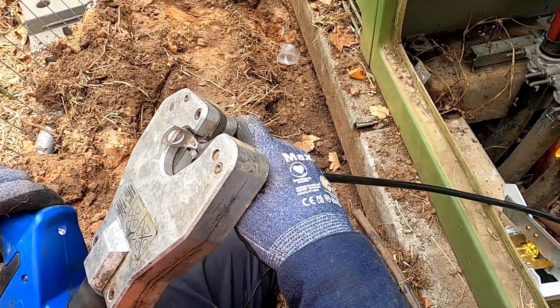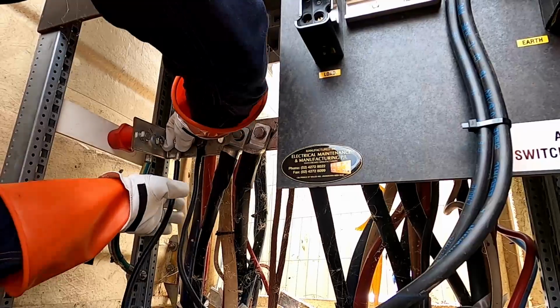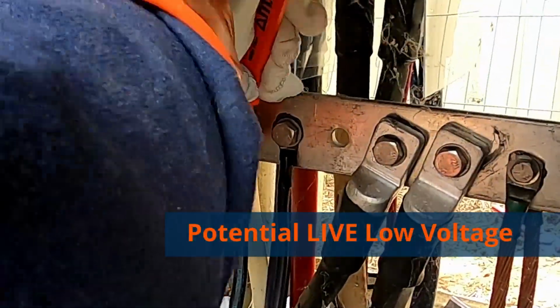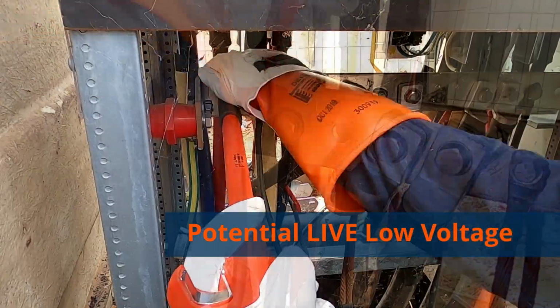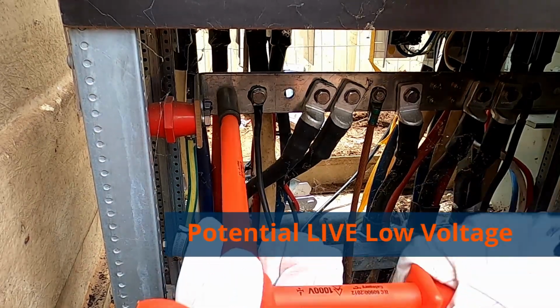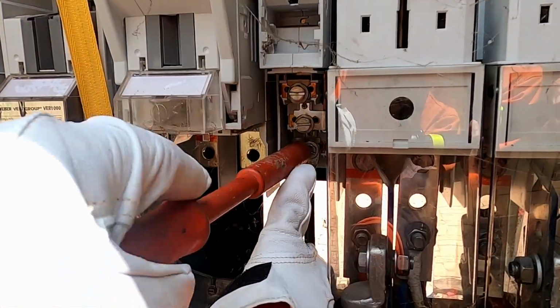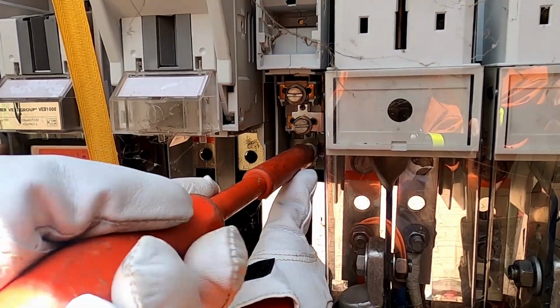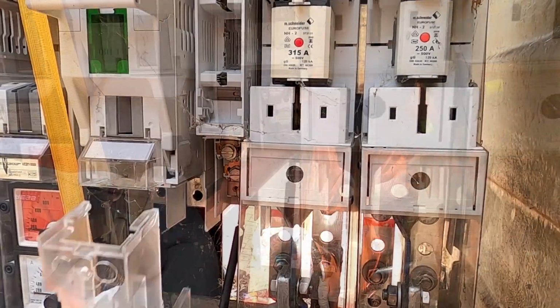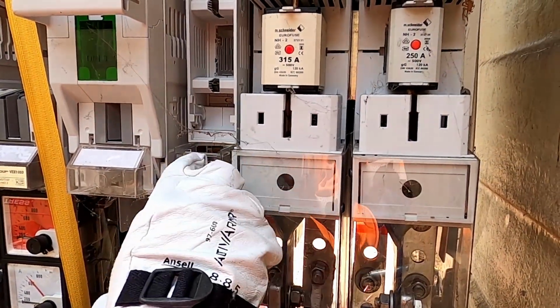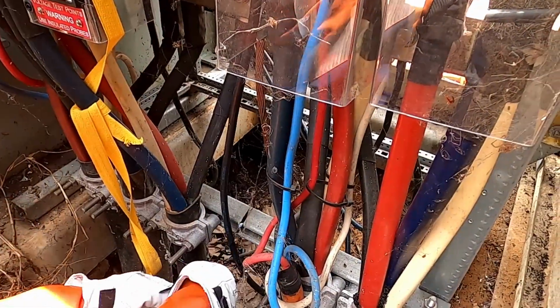Connect the supply neutral to the neutral bar on the switchgear. Please note that LV distributors may be in parallel, so observe live low voltage work procedures as required. Connect the switchgear LV supply panel to a suitable source, in this case an unused streetlight fuse strip. Secure cables adequately in position.